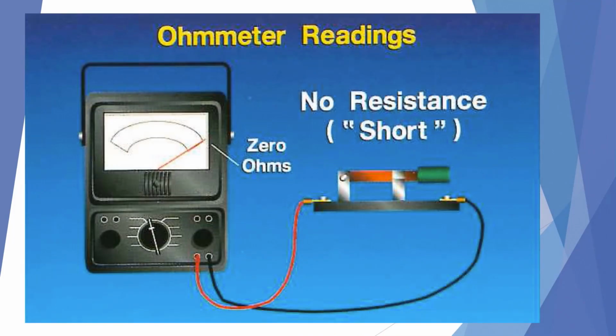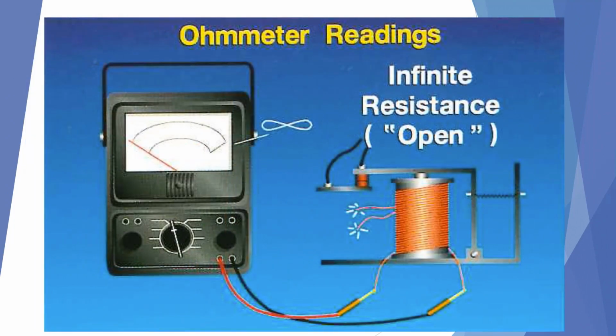Ohm readings are taken with the power on the system turned off so that we can check wires and certain devices to make sure that they are operating correctly. In this particular example, we are seeing a short or no resistance across a closed switch. In this particular example, we're seeing an open circuit. The coil on this device is open, and so therefore a contactor or relay will not be energized because the circuit is open.